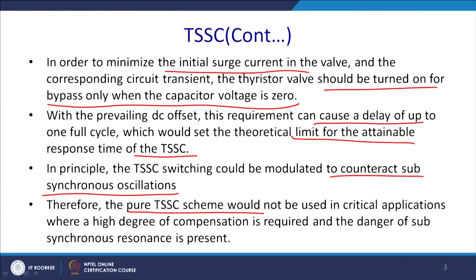Therefore, a pure TSSC scheme could not be used in a critical application where a high degree of compensation is required and the danger of subsynchronous resonance is present, because you are inserting the capacitor, which may lead to reduced impedance, and if the insertion is slow, that leads to subsynchronous impedance, and ultimately you get a delay of at least one cycle. Thus, it is not advisable to use only the TSSC as a series compensator.